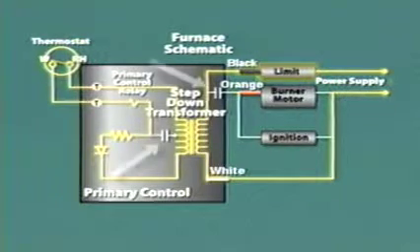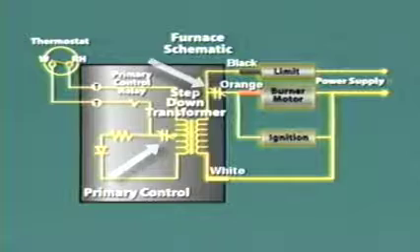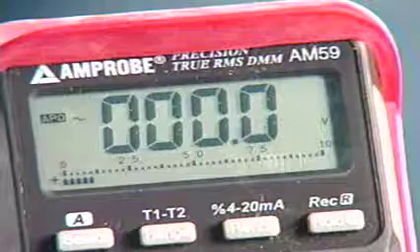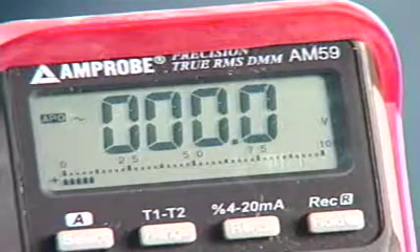Now, in this service call, you know that the burner motor and the ignition transformer are not energized, so you start at the thermostat to see if it has completed the 24-volt circuit to the TT terminals of the primary control. A voltage check at the TT terminals shows zero voltage, which explains why the burner motor and ignition transformer aren't being energized and why the thermostat can't do its job.